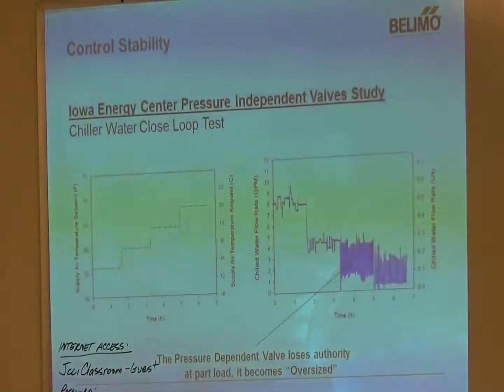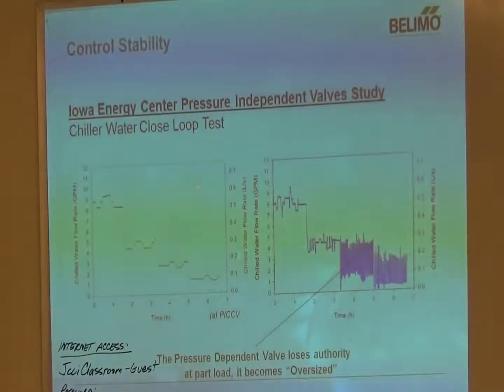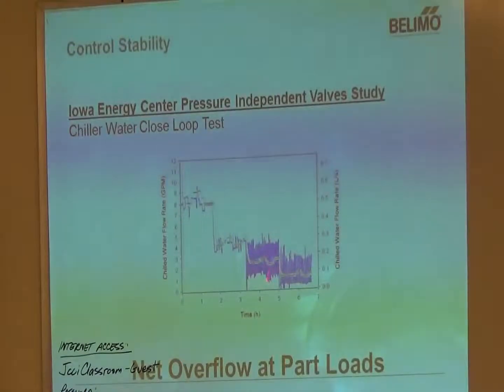Now again, this is from the same study, the Iowa Energy Center. What we're looking at here is the time sequence, and over on the right, we're looking at the pressure dependent valve and all the changes that are made to achieve the necessary space temp. Now on the left, what we're showing is the pressure independent valve in comparison to the pressure dependent valve. We'll overlay these two, and you can see the swings in blue from the pressure dependent valve are all over the place. And I've heard some people say, well, it's going to balance out, the overflow up here versus the underflow. It doesn't. It seems like that would be the case, but we've done studies on it, and they do not balance out. You end up having net overflow.